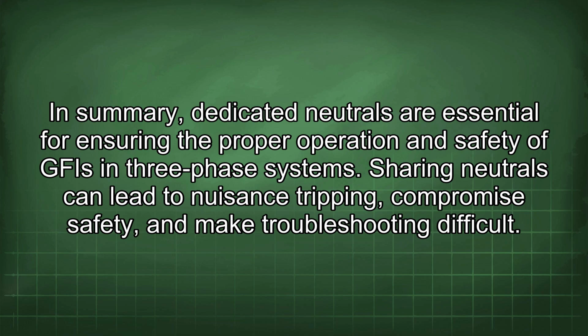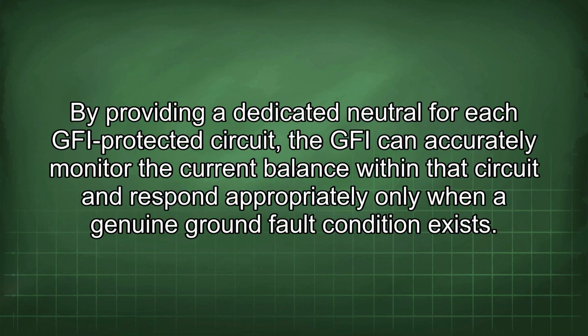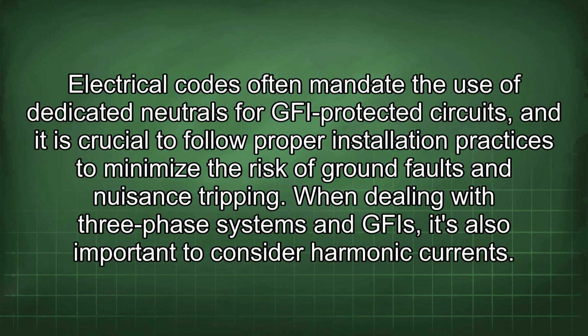systems. Sharing neutrals can lead to nuisance tripping, compromise safety, and make troubleshooting difficult. By providing a dedicated neutral for each GFI protected circuit, the GFI can accurately monitor the current balance within that circuit and respond appropriately only when a genuine ground fault condition exists. The electrical codes often mandate the use of dedicated neutrals for GFI protected circuits, and it is crucial to follow proper installation practices to minimize the risk of ground faults and nuisance tripping.